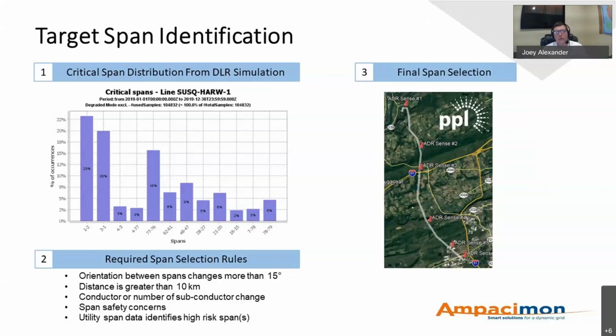And that qualifies those spans as candidates for sensors. We go one step beyond that, we have a set of span selection rules developed over the past 10 to 12 years deploying these sensors throughout Europe. One of the most important rules is that anytime your line orientation changes by 15 degrees, you need at least one sensor in that orientation, to ensure we're getting all angles of the wind speed and understand that wind component really well. We also talk to the utility and find out if they have records of any spans that have been troublesome, had safety concerns, or might be high risk because they're going over something.